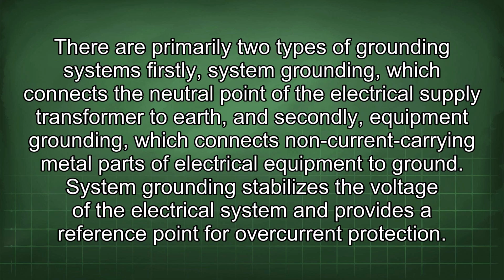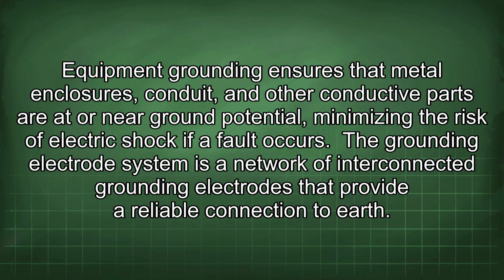There are primarily two types of grounding systems. Firstly, system grounding, which connects the neutral point of the electrical supply transformer to earth, and secondly, equipment grounding, which connects non-current carrying metal parts of electrical equipment to ground. System grounding stabilizes the voltage of the electrical system and provides a reference point for overcurrent protection. Equipment grounding ensures that metal enclosures, conduit, and other conductive parts are at or near ground potential, minimizing the risk of electric shock if a fault occurs.